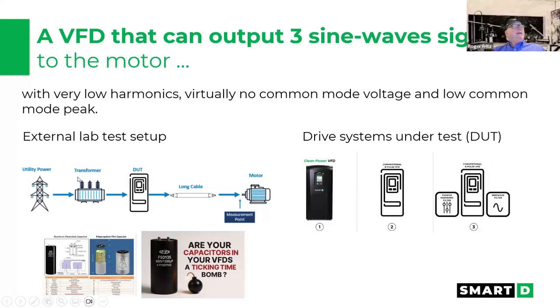So, at the end of the day, we have very low harmonics, no common mode voltages, and this is all from external lab tests that were done. We have no problem with long leads. We don't require anything between us and the transformers. Another advantage is that we don't use electrolytic capacitors. In a standard VFD, you have electrolytic capacitors, and if you read the fine print, it says that within 10 years, you're supposed to be changing these capacitors because the film ends up drying out. We actually use more of an oil-filled type capacitor because we don't have all of those high harmonic ripples that we've got to clean up.